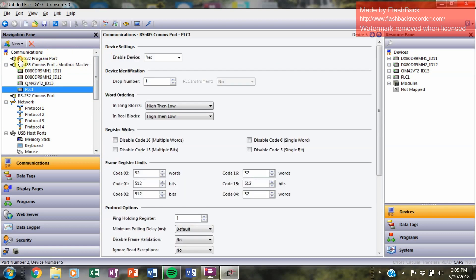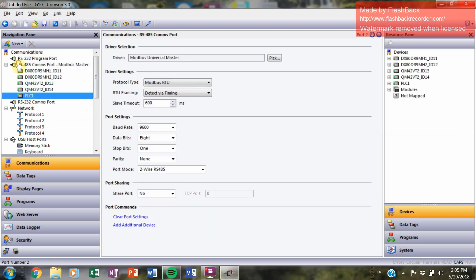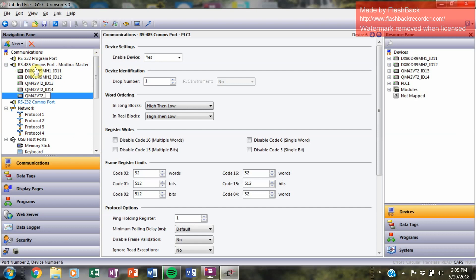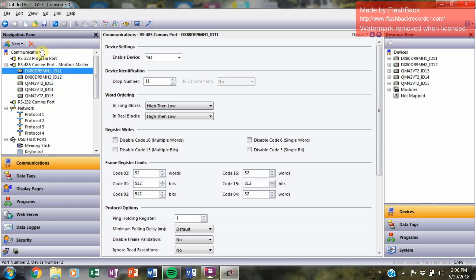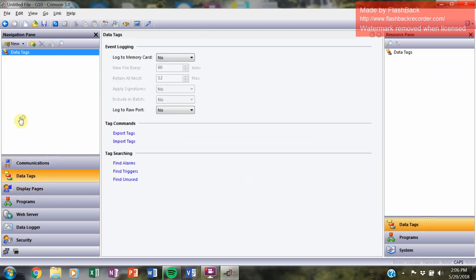Let's add device number 14 — QM42VT2 underscore ID14 — and give that drop number 14 as well. Our final device is number 15, QM42VT2 underscore ID15, with drop number 15. So to recap: slave IDs one through ten are reserved for Banner radios; we start at 11 for the gateway, 12 for the node, and 13 through 15 for the three vibration sensors in parallel. That's the comms port setup complete.